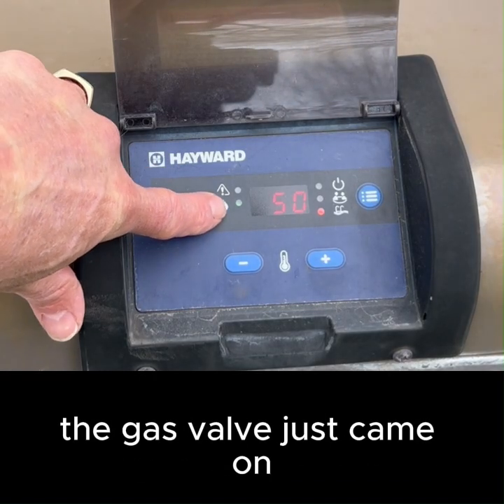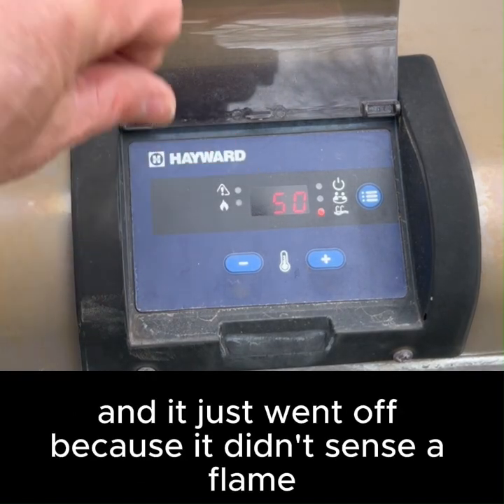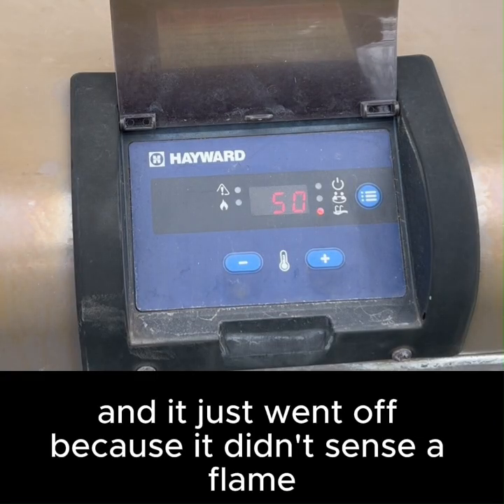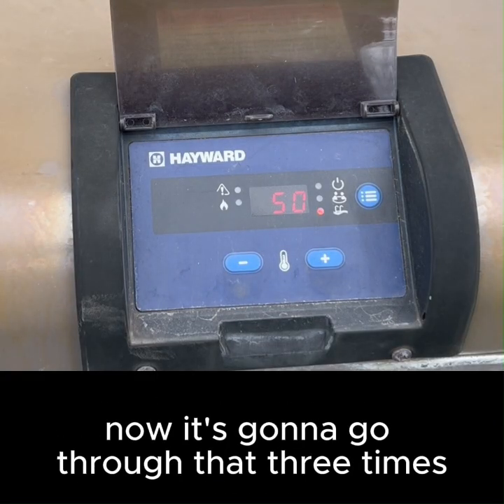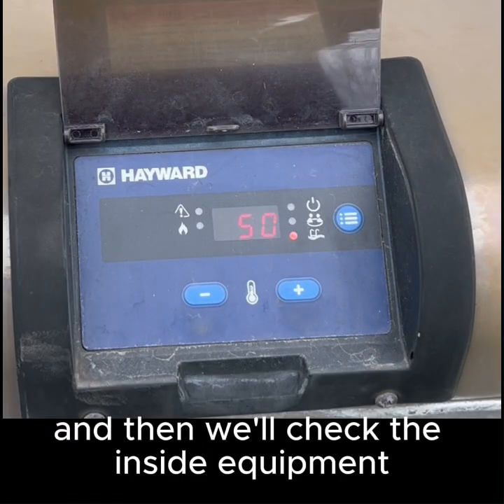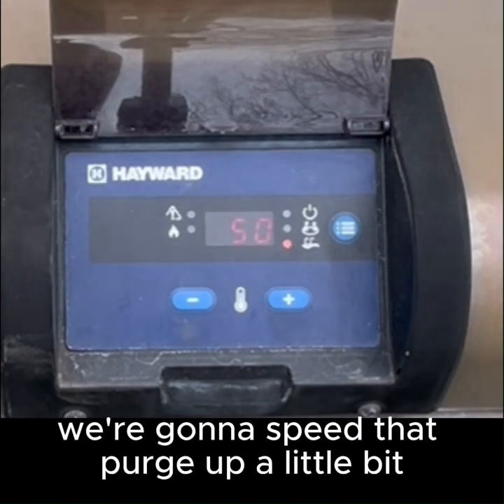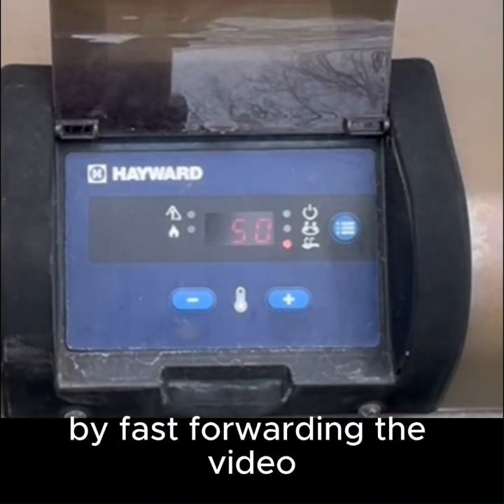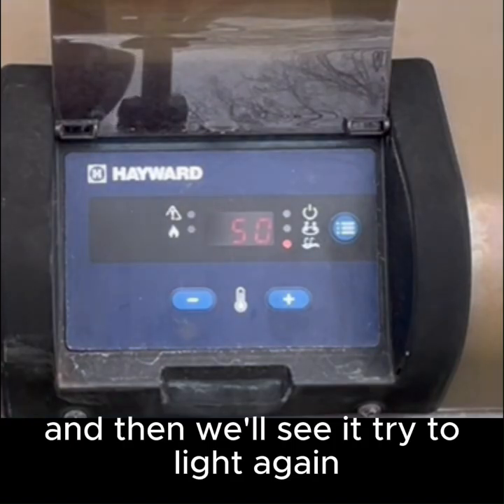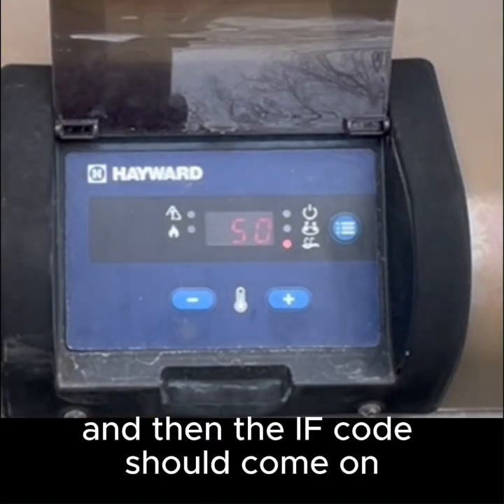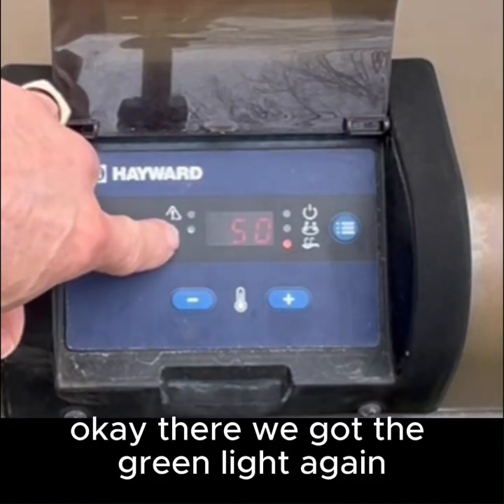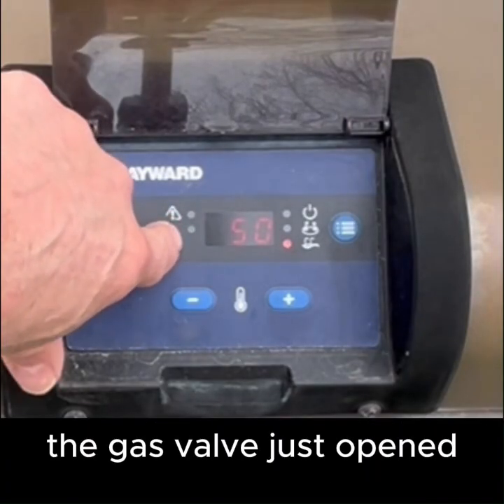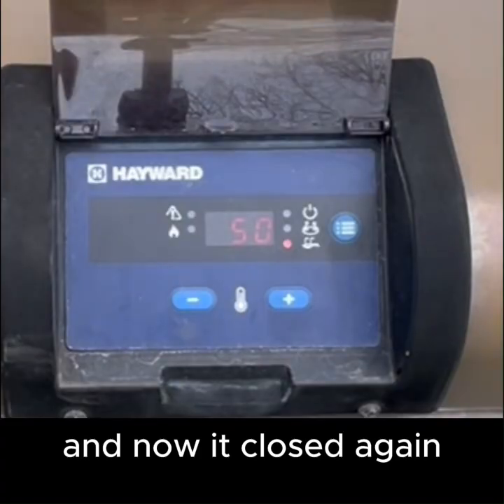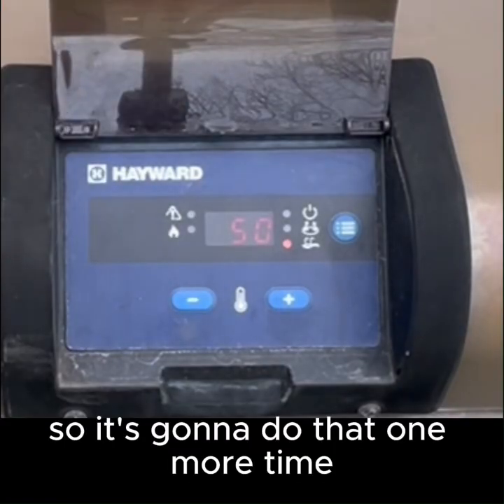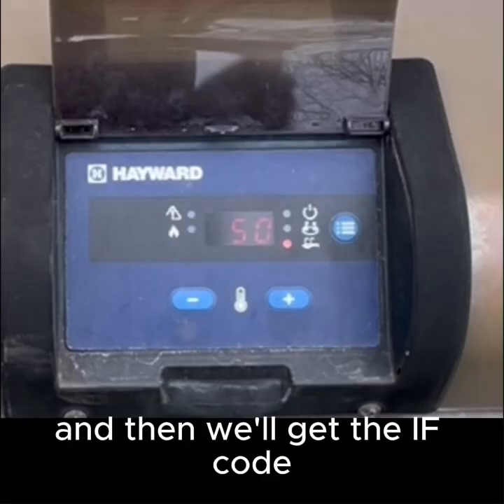So that'll prove that the gas valve is working. There you can see the gas valve just came on, and it just went off because it didn't sense a flame. Now it's going to go through that 3 times, and then we'll check the inside equipment. We're going to speed that purge up a little bit by fast forwarding the video, and then we'll see it try to light again, and then the IF code should come on. Okay, there we got the green light again. The gas valve just opened and now it closed again. So it's going to do that one more time, and then we'll get the IF code.